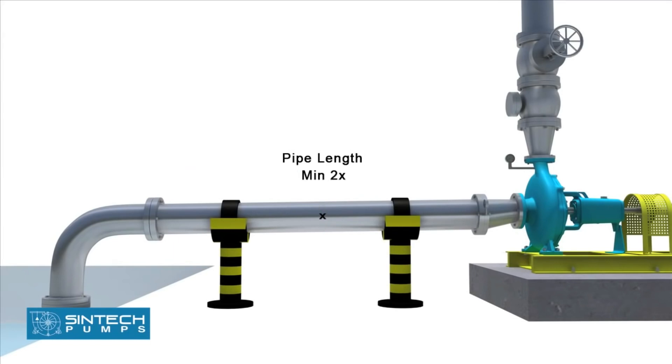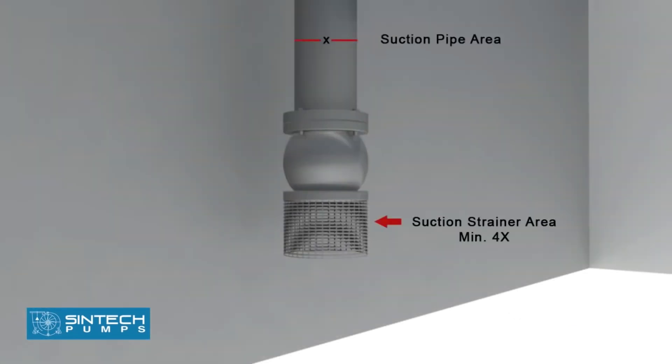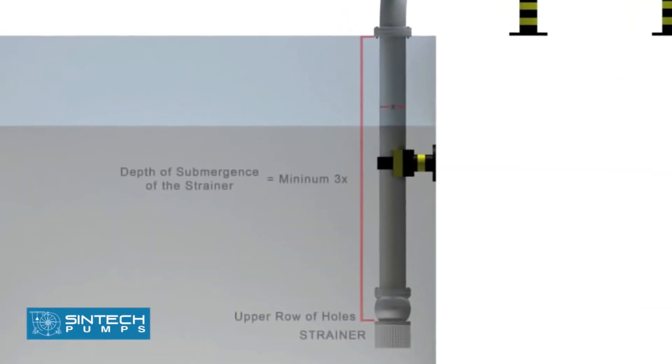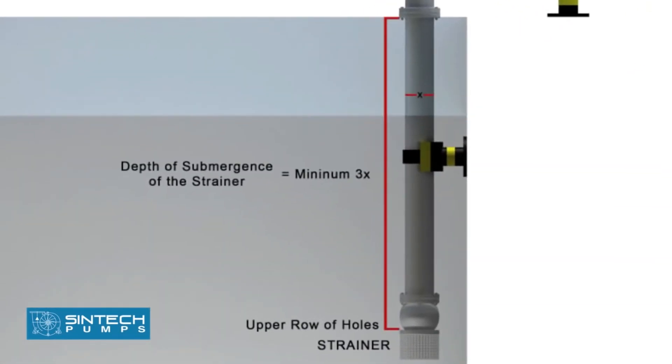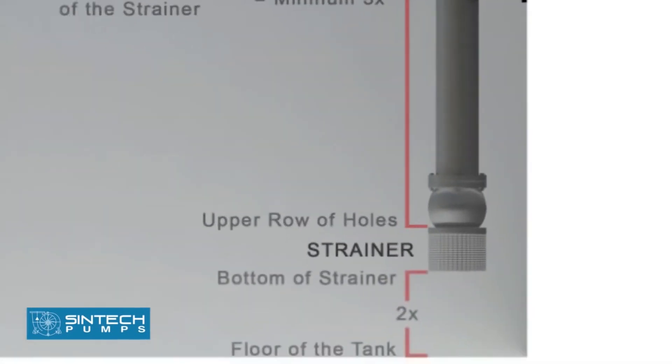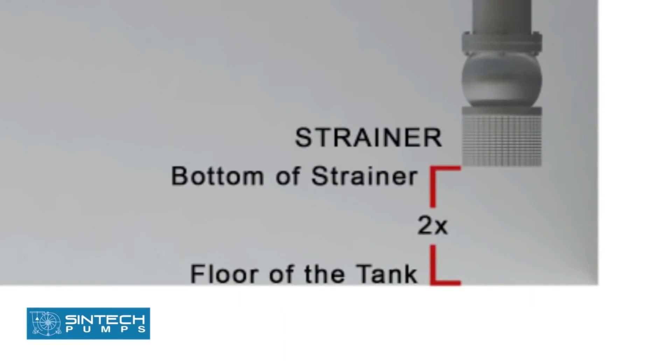The suction strainer must be at least four times the suction pipe area and the mesh size should screen out solid particles that could clog the impeller. The minimum depth of submergence of the strainer should be at least three times the pipe diameter measured from upper row of holes of strainer. The distance between the bottom of strainer and the floor of the tank should be considered as two times the pipe diameter.